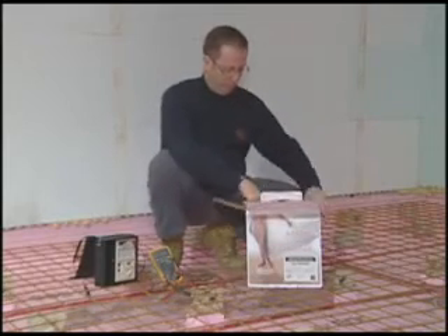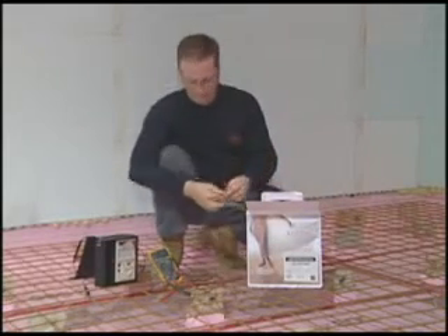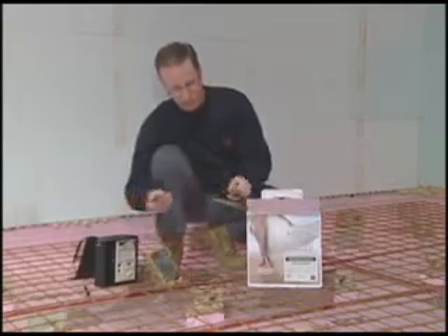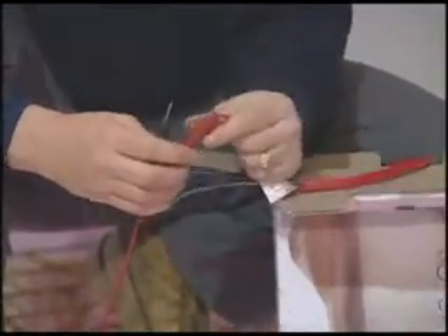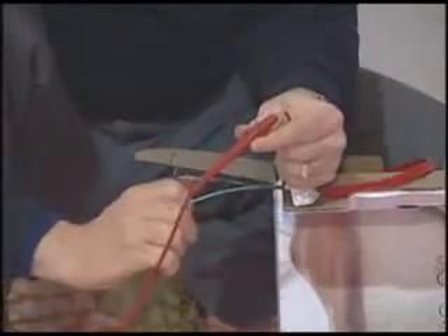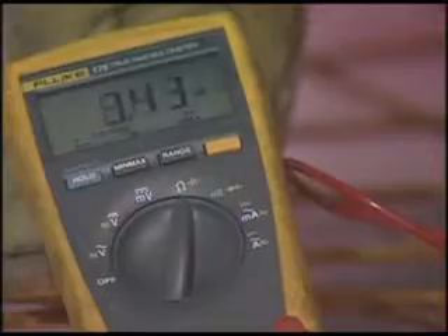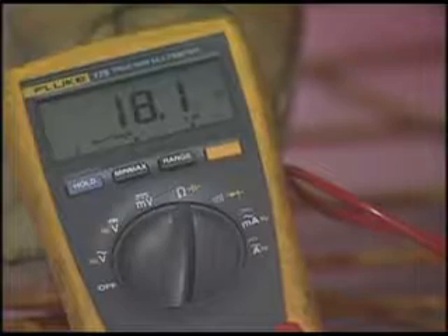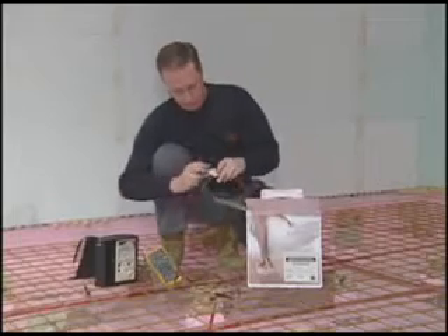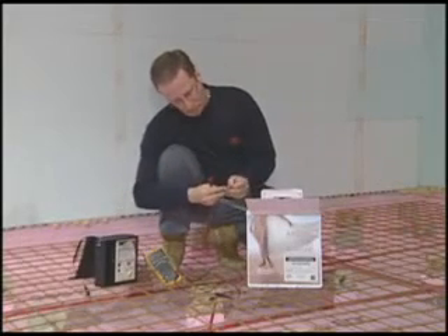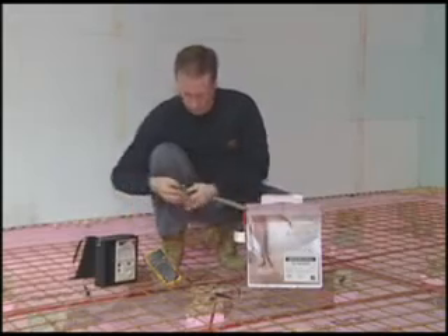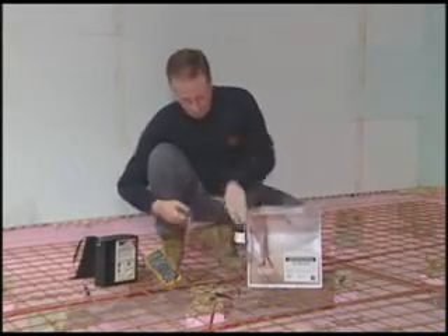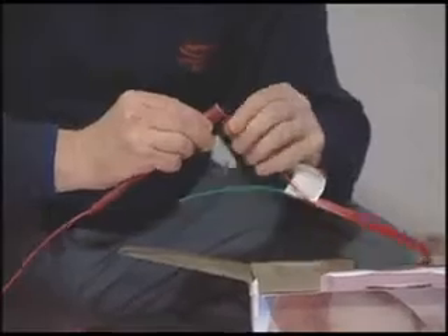Before starting to lay out your heating cable, verify its resistance with a multimeter or ohmmeter. The resistance should match what is indicated on the identification label attached to the cable's end. You must also check the integrity of the cable's insulation with a megometer. A reading of infinity confirms that the cable is in perfect condition.